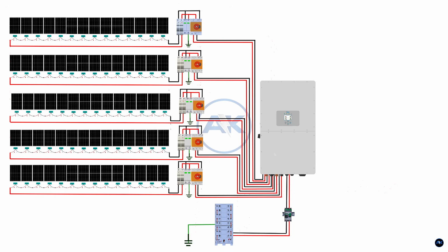After the power cables are connected, we connect the communication cable. The communication cable links the battery BMS to the inverter, usually using a CAN or RS-485 connection. This cable allows the inverter to read battery voltage, current, state of charge, and protection status. Plug the communication cable into the battery communication port and the corresponding port on the inverter. Make sure the connection is firm and the correct protocol is selected later in the inverter settings.